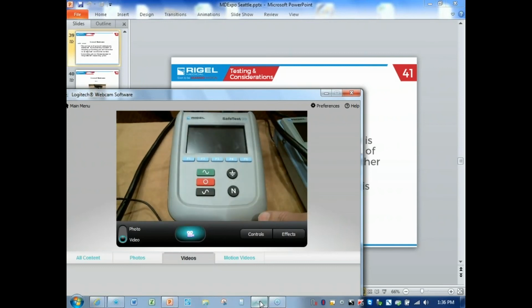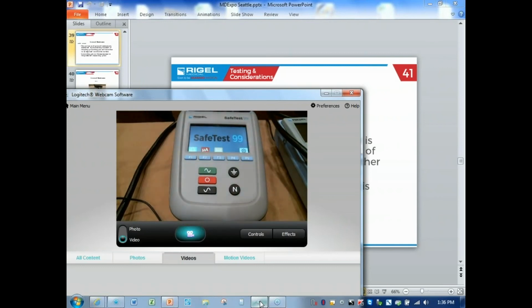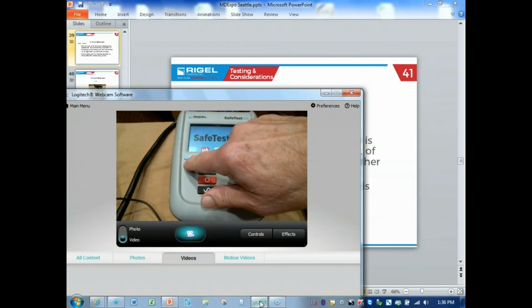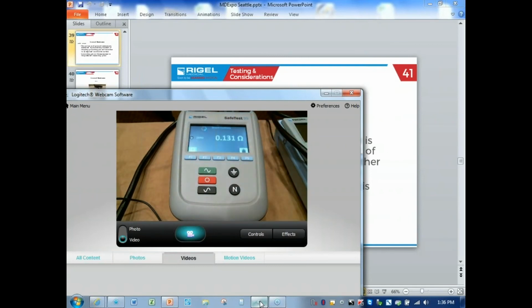Watch how quickly this thing powers up. Boom, ready to go. So when you look at safety analyzers, you always have the power coming into the safety analyzer. You have the socket for the device under test, and you have the plates for your test cable. And in this case, there are 2, so you have the ability to do point-to-point testing. We take our test cable, we can connect it to something that is internally connected to the earth ground. So we're going through metal through our ground pin, which is going to the safety analyzer. And I hit this button, and there you have it.